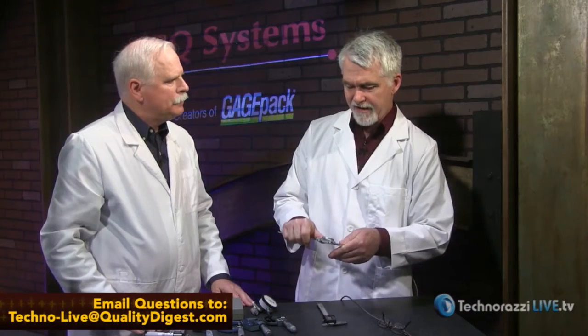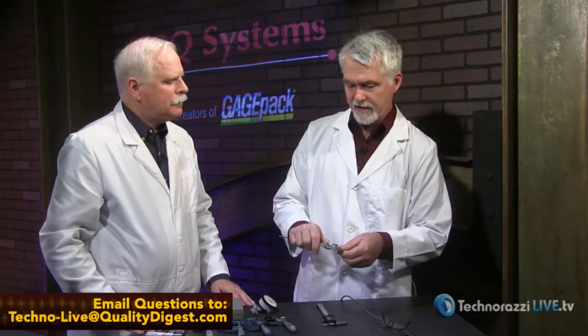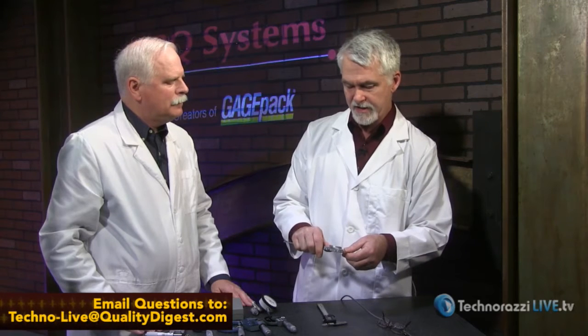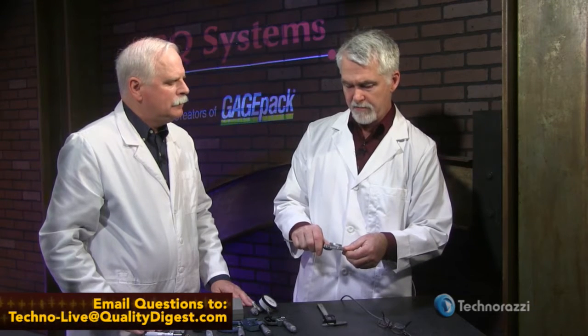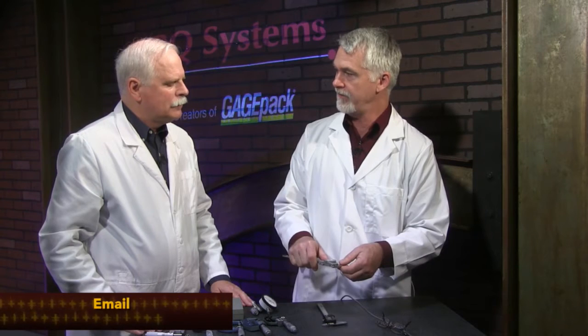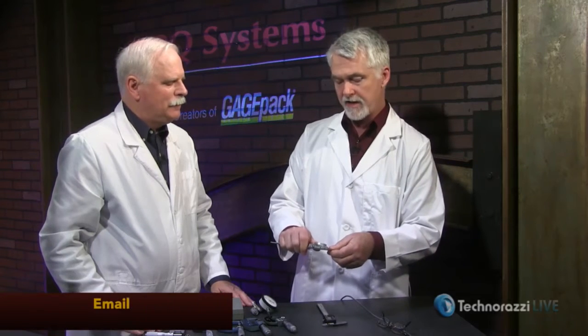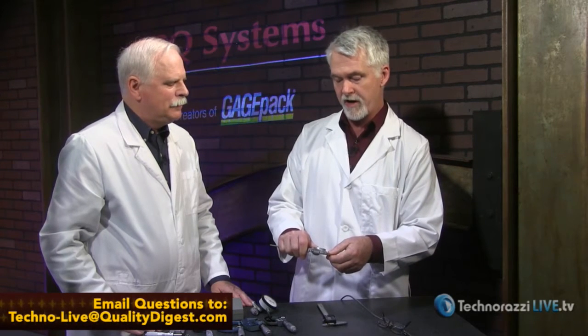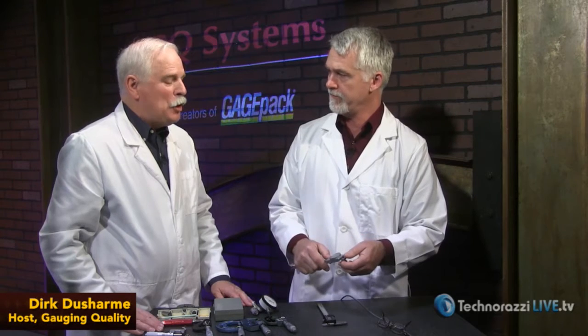Wait a minute. I thought on a mechanical or dial gauge you could kind of read in between the digits, right? A digital just gives you a number. But I mean, I can guesstimate that's 1.5 units. You can read it, but the accuracy is 1 division. So you're not doing yourself a favor saying that's 125.4 or 125.5.